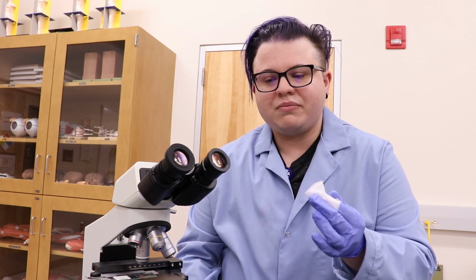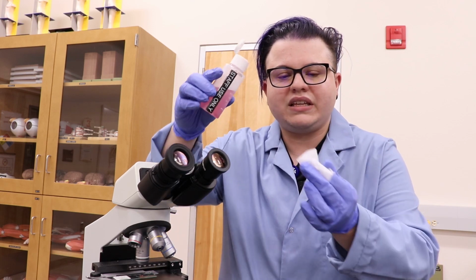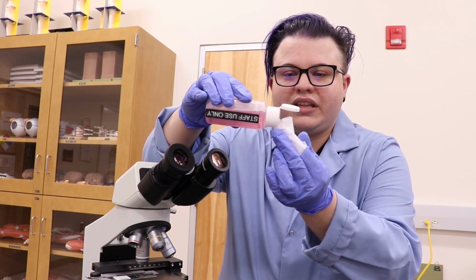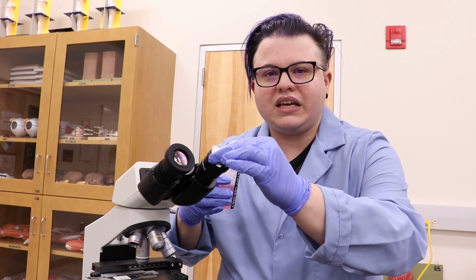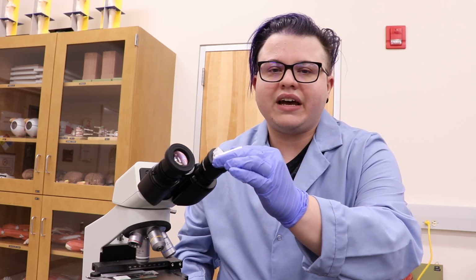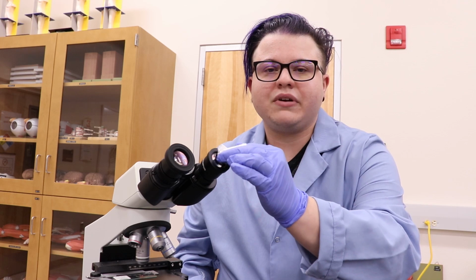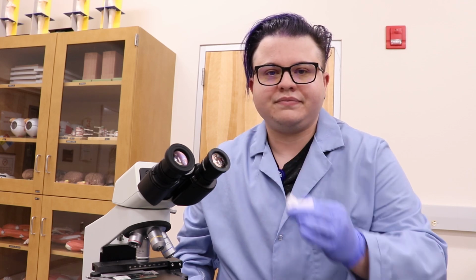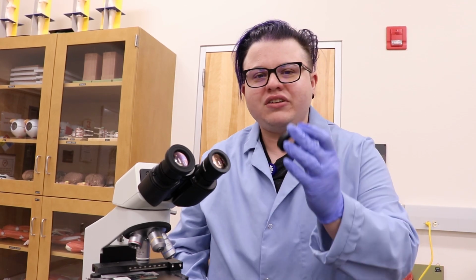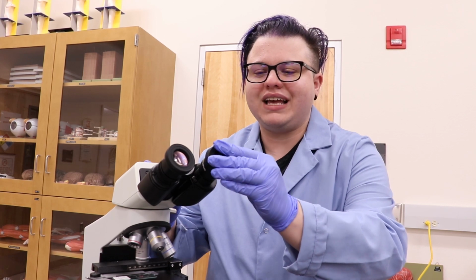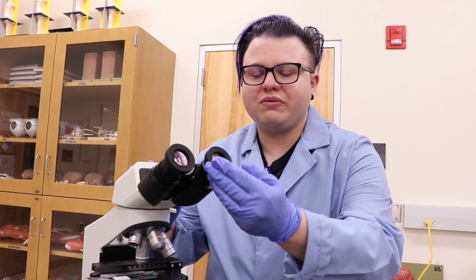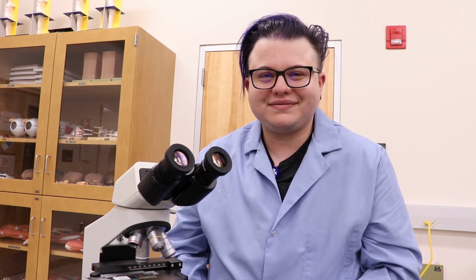If you're having trouble removing any residue from the eyepiece with just the lens paper, you can take some of the optical lens cleaner, just a drop, onto the lens paper and use that to clean the eyepiece. You'll want to dry it afterwards with a clean piece of lens paper. When you're finished, you can put the rubber ring back on by just gently pressing it to the rim. It should clip into place.